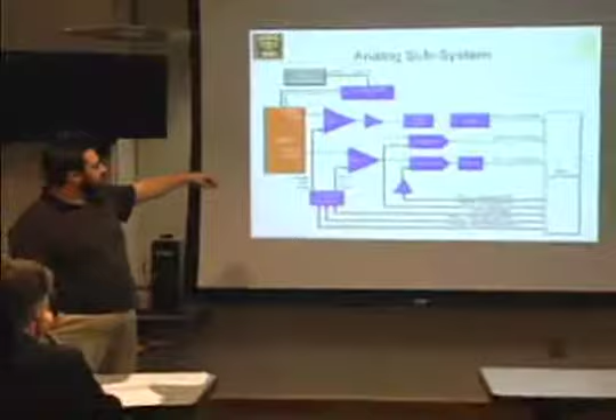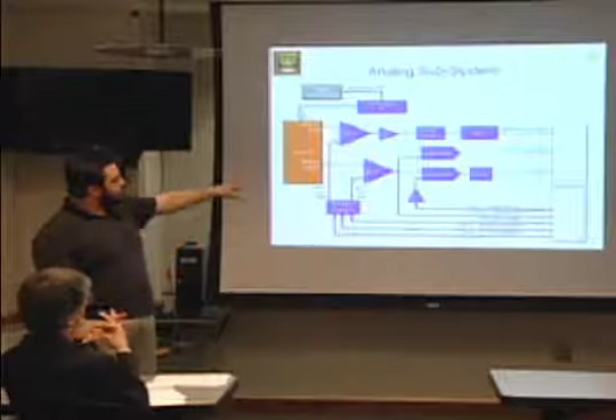In the analog subsystem, as I said before, we receive high voltage from that high voltage supply. We go ahead and split and isolate that into 3 distinct signals. One of them is not instrumented, it's just fed to the detector directly. Another one is instrumented as our event line. An event coming out of the detector is a small amplitude positive current pulse. And so we feed that into a charge-sensitive preamplifier, the A225. Because that's an inverting amplifier, we invert the signal on its output, so we're working with a positive signal again, feed it through a peak hold, and then acquire it with an ADC. The way we know that there's an event to acquire is we also feed it into a comparator, and the output of that comparator triggers an interrupt in our microcontroller.